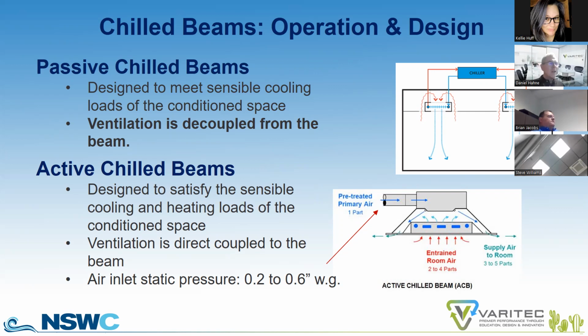An active chill beam is a ducted device where air is injected into a two-tiered plenum box. Air is injected into the upper tier and injects air at high velocity on opposite sides of a horizontal coil located in the lower tier. That high velocity discharge through air nozzles on either side of the coil creates a negative pressure zone above the coil that draws room air across the coil, transferring the sensible heat energy in that space to the chill water loop where it is removed from the building. Air inlet static pressures on active chill beams are between 0.2 and 0.6 inches. Some areas you might even be able to get up to 0.7 depending on the manufacturer that you use.